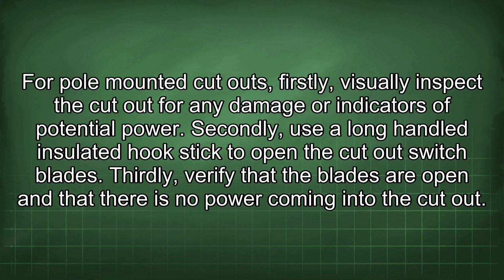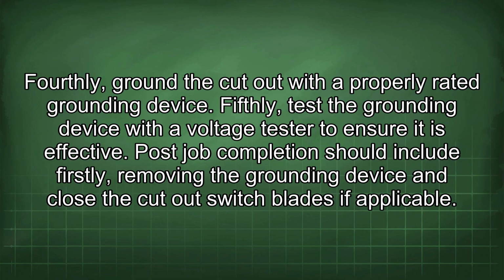For pole-mounted cutouts, firstly, visually inspect the cutout for any damage or indicators of potential power. Secondly, use a long-handled insulated hook stick to open the cutout switch blades. Thirdly, verify that the blades are open and that there is no power coming into the cutout. Fourthly, ground the cutout with a properly rated grounding device. Fifthly, test the grounding device with a voltage tester to ensure it is effective.